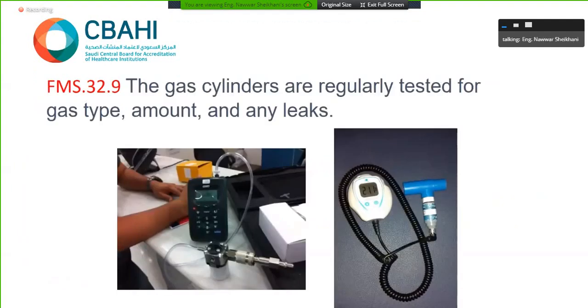The gas cylinders are regularly tested for gas type, amount, and any leak. Actually, we get frequent questions: since we are receiving these cylinders from the supplier, from the factory, why should we test them? As a matter of fact, a few years ago, we informed the supplier in our region that Entonox, which is used in labor and delivery, I think, should be 50% oxygen and 50% nitrous oxide. We found by our tools that it was 48 and 48.